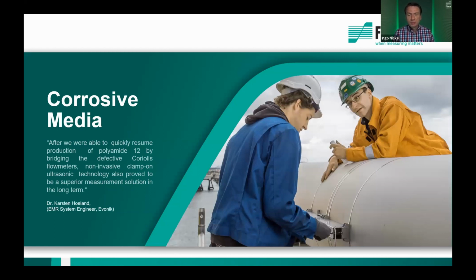Another very important challenge within chemical applications or chemical plants are corrosive media. They are always critical points in the selection of a suitable material of construction for the process equipment, and particularly inline measurement equipment are crucial points. But if you're using clamp-on ultrasonic flow meters, they do not come in contact with the media, and this avoids the selection of expensive materials for the wetted parts. A very good example is the metering of sulfuric acid. We have a lot of plants equipped with our clamp-on flow meters for sulfuric acid production.